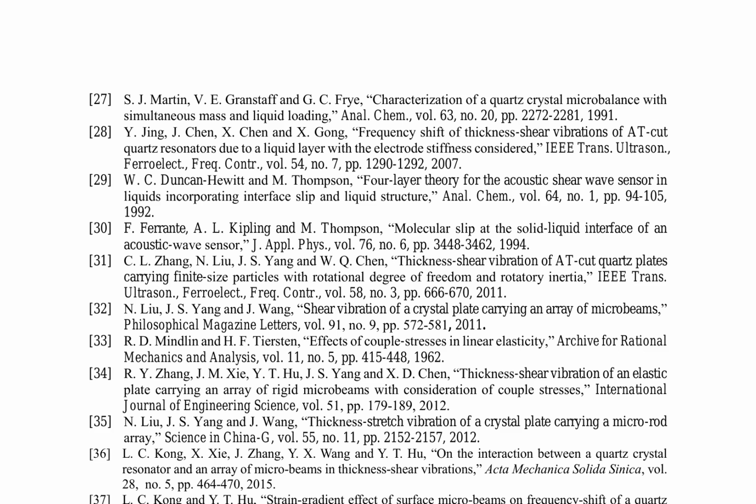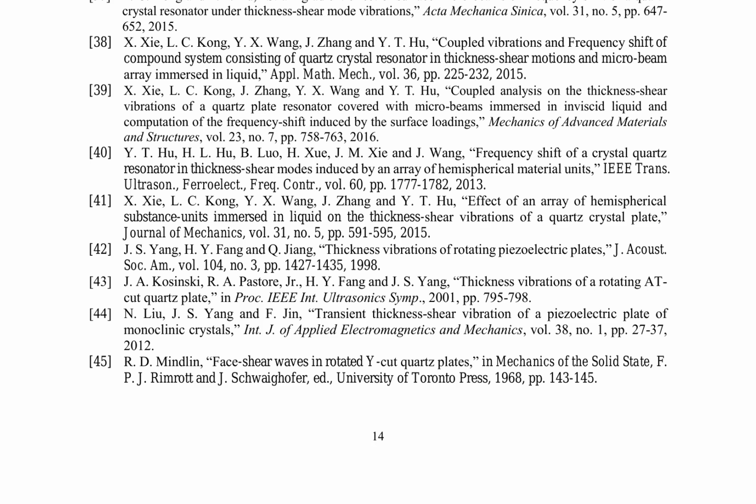The influence of liquid properties, including viscosity, density, and surface tension, on the quartz crystal's frequency response has been extensively investigated. Research has shown that increasing viscosity and density led to a decrease in the resonance frequency, while surface tension affects the frequency response in a more complex manner.